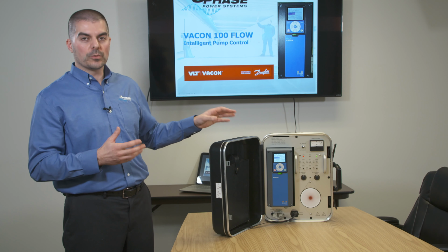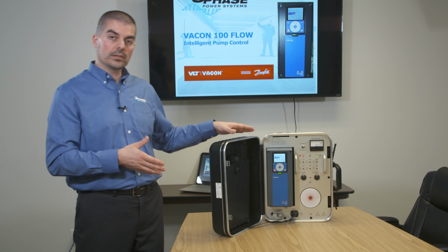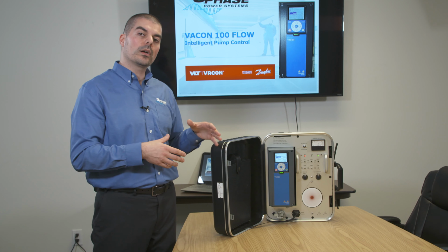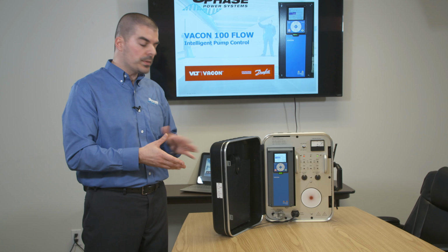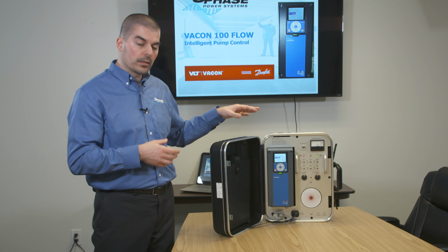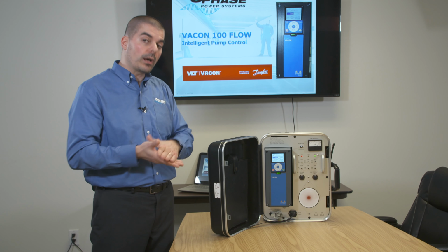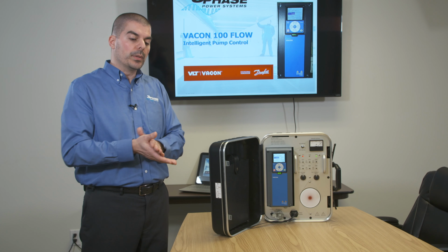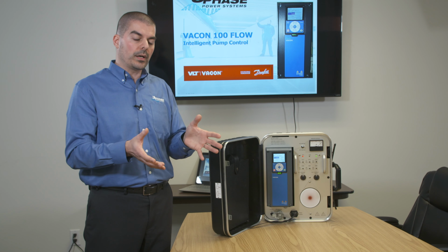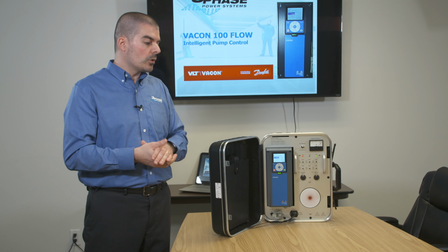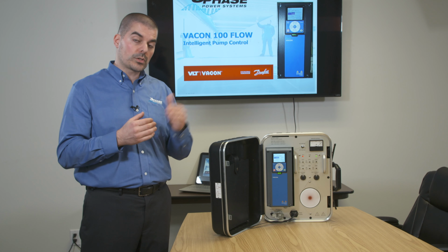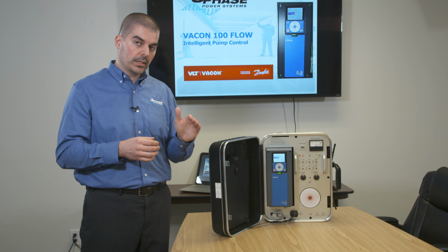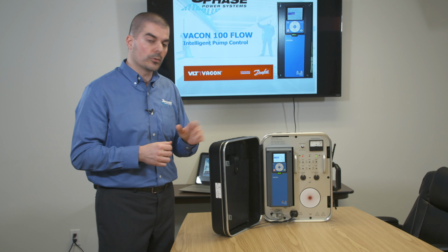So we saw how the drive runs. Now we're going to stop it and program soft fill. What this means is that the PID controller right now ramped up to 60 hertz immediately, but we don't want the water pipes to have water hammer, so we're going to program the drive to do a soft fill of the pipes gently to eliminate water hammer, and we'll show how to do that.